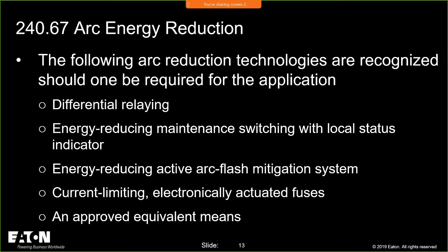Now that approved equivalent means has been in there since day one, and the reason it is there is because they don't want to stifle innovative solutions in the area of electrical safety and reducing arc flash. I may come out with a Van Ducky tomorrow that is the best Van Ducky you've ever seen. It's a UL listed Van Ducky, and it's the fastest acting arc current clearing Van Ducky that it defies the laws of physics. It's not in this list, but it should be able to be approved. So that approved equivalent means, we're going to cover ways to help your AHJ, your authority having jurisdiction, approve it. And these are just, again, my opinions on how I would do it. We're going to talk a little bit about that moving forward as well.